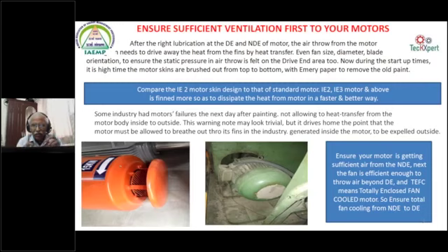You come across any type of industry, whenever they say out of 10 motors that have failed, almost 3 or 4 motors failed because of the backside fan blade, which is made of a very ordinary plastic. A lot of excellent engineering polymers have come, which are very strong and able to deliver excellent static pressure and CFM. That is not fitted now.